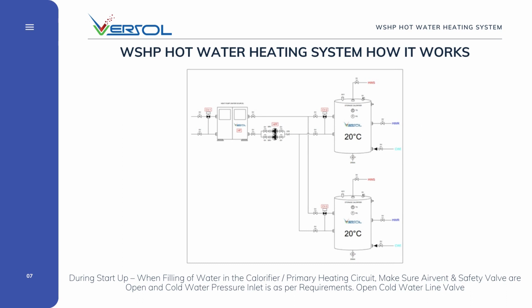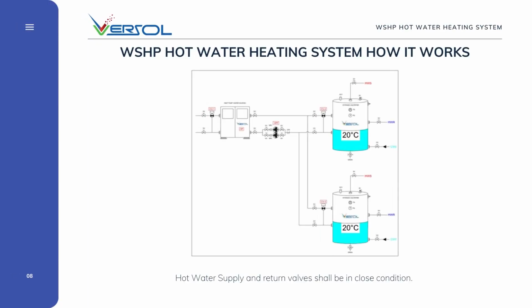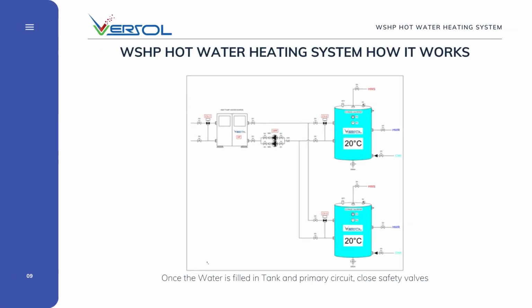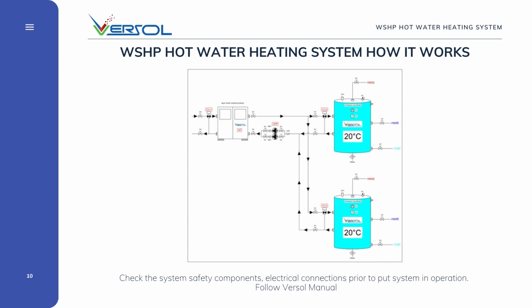During startup, when filling water in the calorifier and primary heating circuit, make sure the air vent and safety valve are open and the cold water inlet pressure is as per requirements. Open the cold water line valves. Hot water supply and return valves shall be in closed condition. Once the water is filled in the tank and primary circuit, close the safety valves and air vents. Check the system safety components and electrical connections prior to putting the system in operation. Follow the Versol manual.